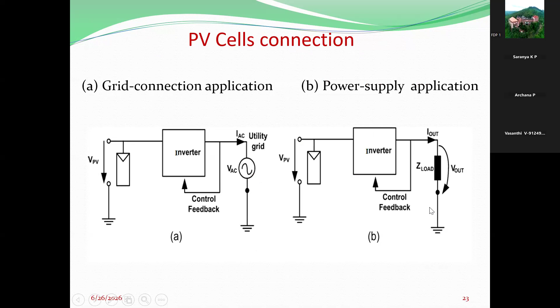Then inverter families: central inverters, module-oriented or module-integrated inverters, and string inverters. These are some of the advanced inverter technologies. Central inverters are connected in parallel and/or series on the DC side, and one inverter is used for the entire PV plant, so control complexity is slightly reduced, but reliability is affected since anything happening to that one inverter affects the whole plant. The nominal power of this topology goes up to several megawatts.